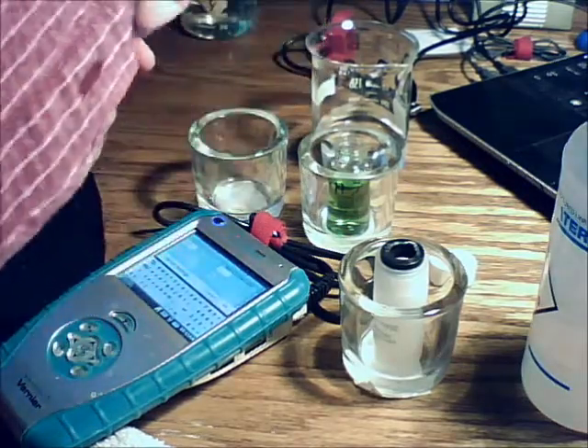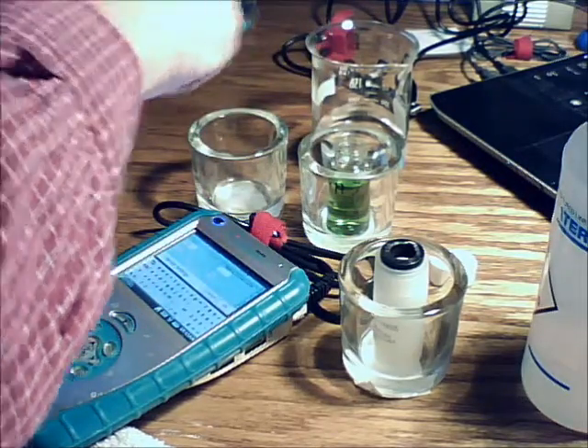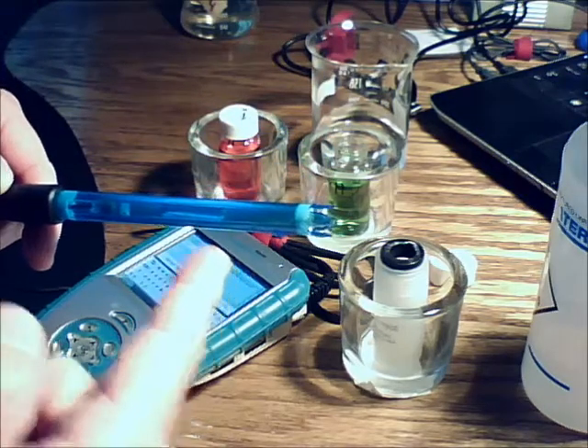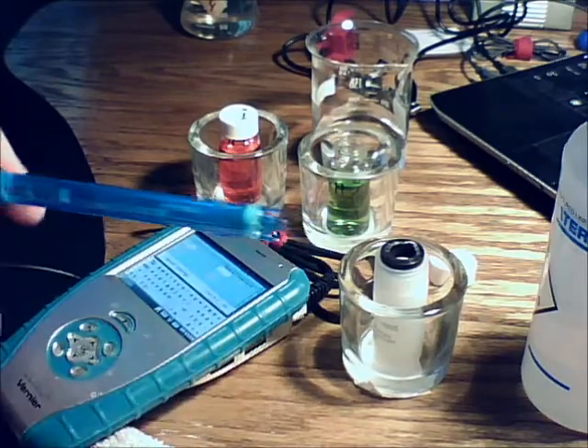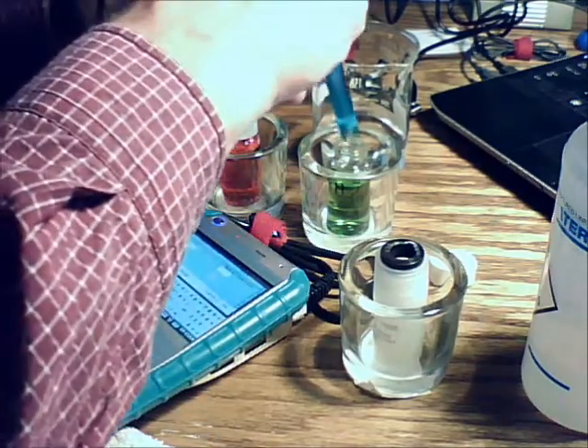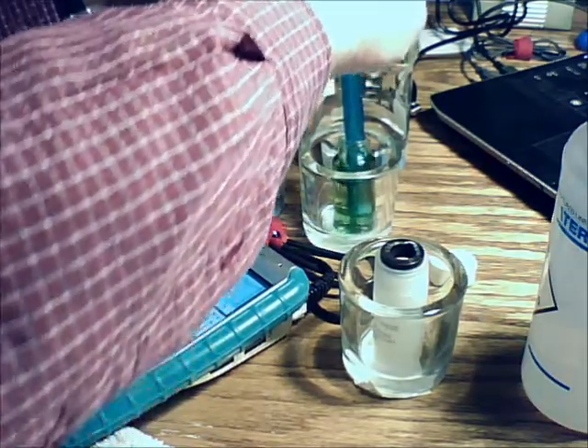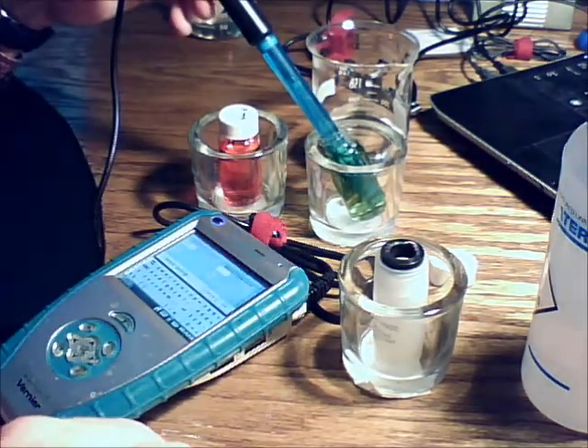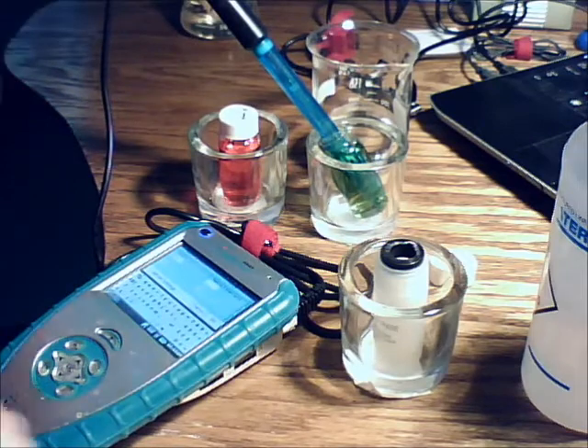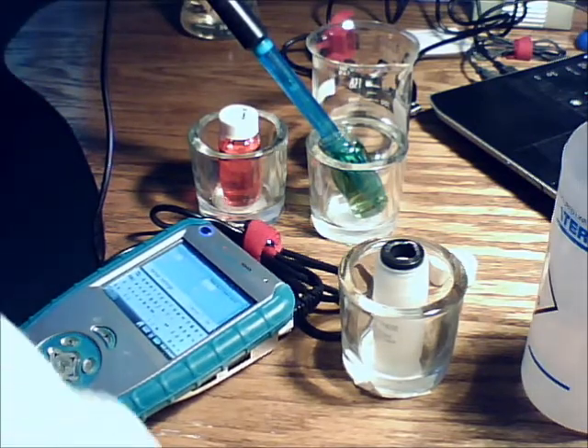Keep these things capped, okay? Don't leave them open, and don't let this pH probe get dry. If you leave it on a lab table, it gets contaminated. If you leave it out in the air, it gets dry, and we don't want it to get dry because then it won't work. Put it in the pH 7 solution, and they're color-coded. pH 4 is sort of that peach-looking or orange-looking, and pH 7 is a green-looking solution.